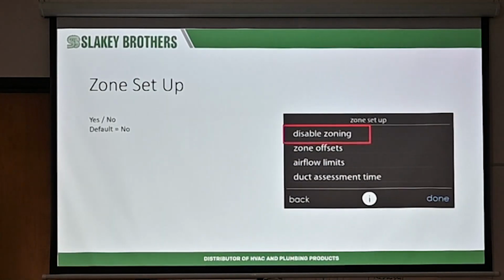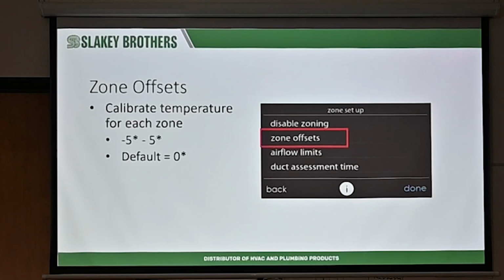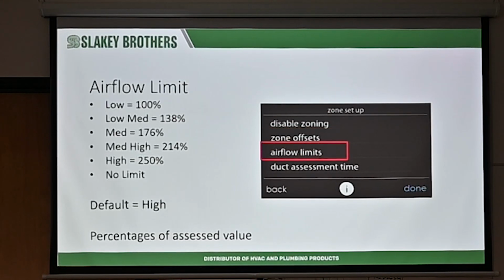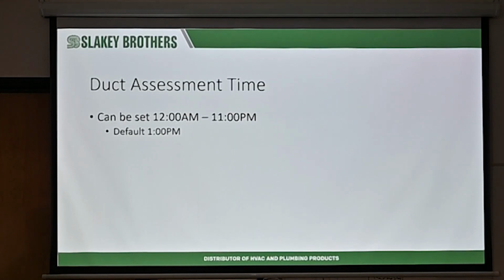Any kind of adjustment to zoning. If you got a problem, maybe some dampers are broken, and you got to replace dampers, you got to order them. You can disable zoning so they all stay open, and all it does is work right off of the main controller. Any temperature offsets, airflow limits, and as well you can do a duct assessment, when you can tell it when to do the duct assessment. Otherwise, it generally does a duct assessment every day about 1 p.m.